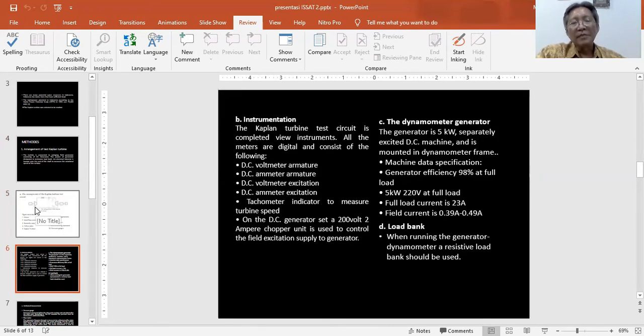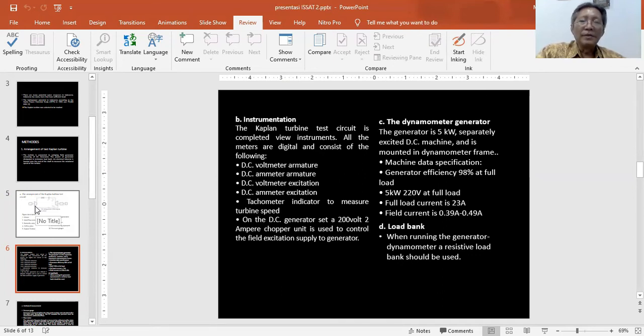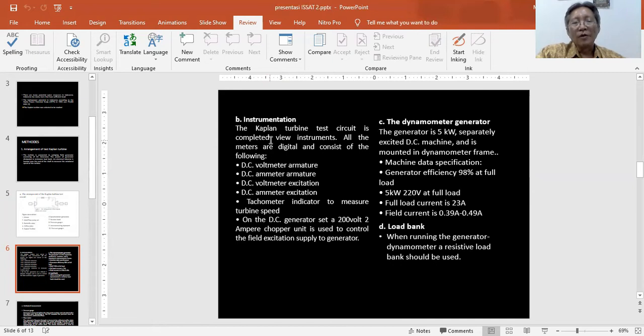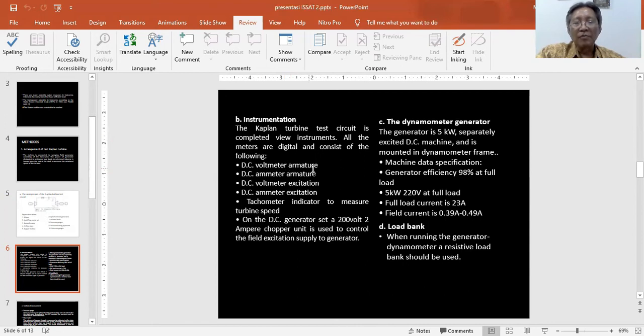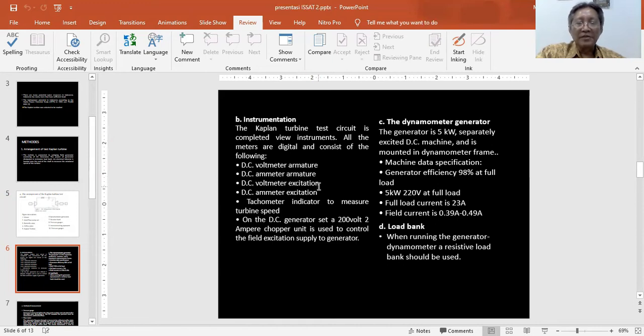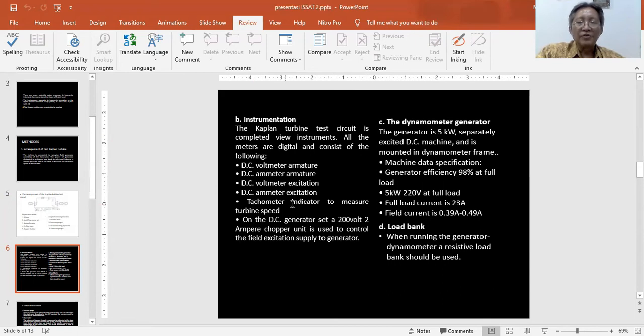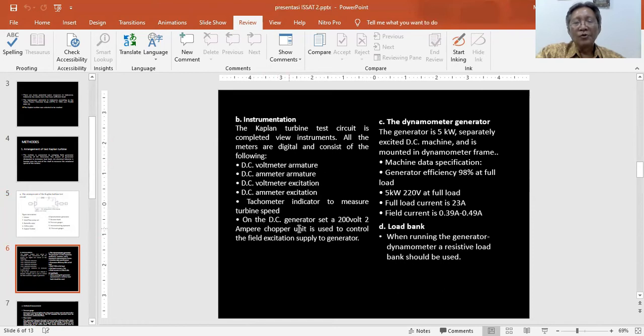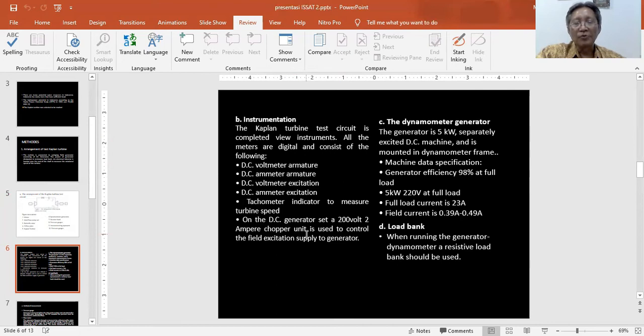In the test arrangement, a lot of instrumentation is set. We have a DC voltmeter armature, DC ammeter armature, DC voltmeter excitation, DC ammeter excitation, and tachometer indicator to measure turbine speed. Also on the DC generator set, a 200 volt 2 ampere supply unit is used to control the excitation supply to the generator.